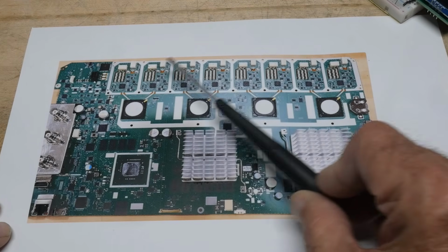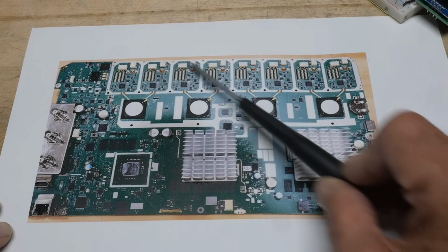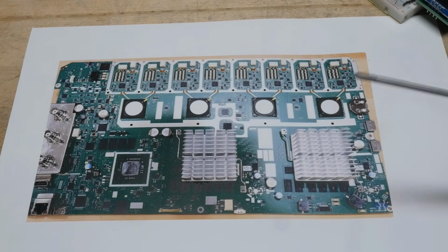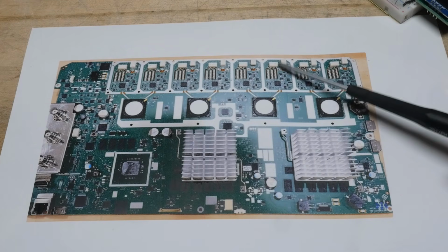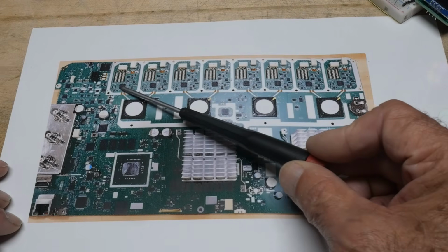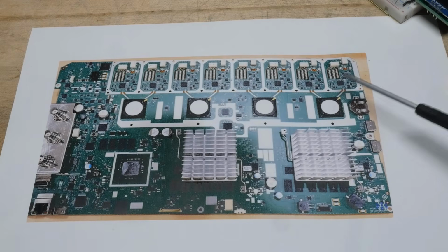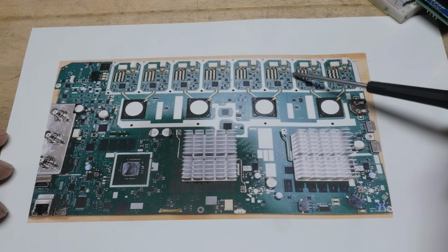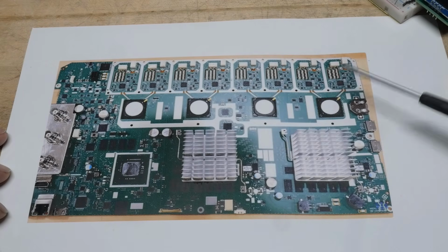Each channel has its own input section, right? There are attenuators on each channel, and some relays for AC coupling, DC coupling, grounding, that kind of stuff, and the 50 ohm input. Those are what the relays do. Then there are the attenuators that set the ranges, and then there's a preamp. This chip here is a custom chip for Rohde & Schwarz. And there are some other little op amps and things in here that add DC offsets. Each of the 8 channels has an entirely identical input section.